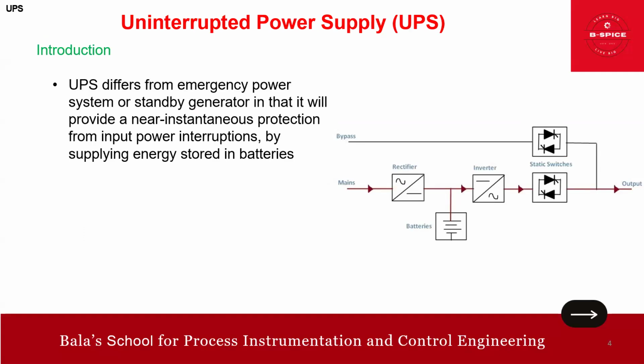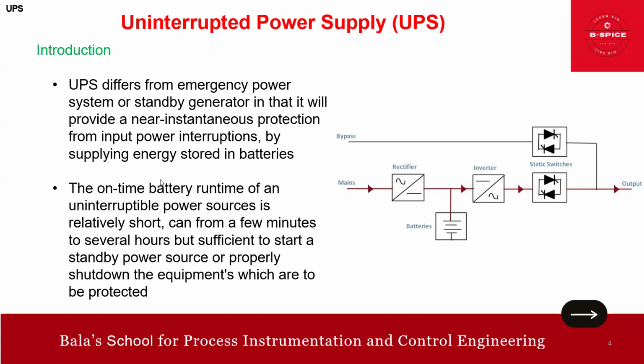One point I want to inform you: this UPS differs from the emergency power or standby generator, the EDG. The UPS provides near instantaneous protection from input power supply interruption by supplying the energy stored in batteries. So there is no interruption - near instantaneous protection. That is what differs it from the emergency power.